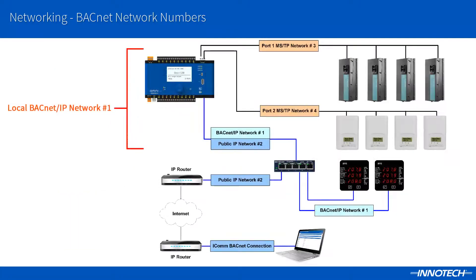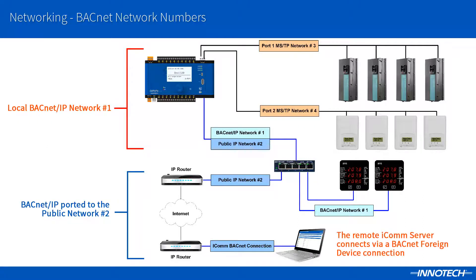The public network is used for access to the site via a router. The public BACnet network is another segment with a network number 2 by default. iComm can connect to this site via a BACnet foreign device connection, and all BACnet devices are discovered via this connection.